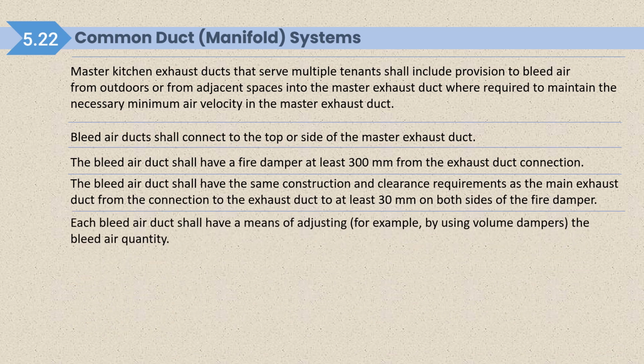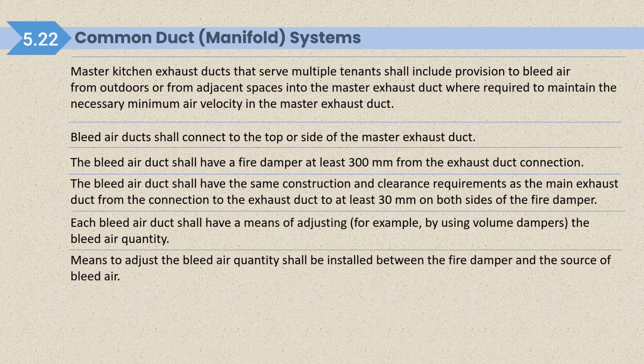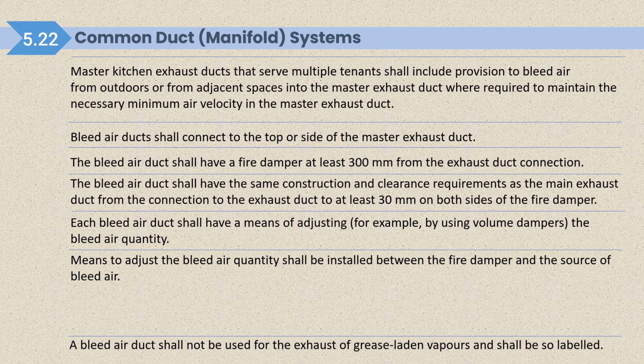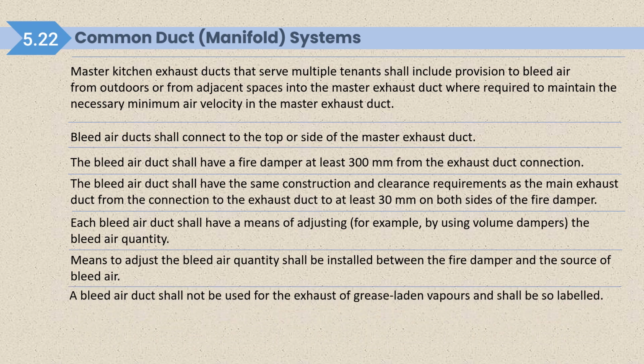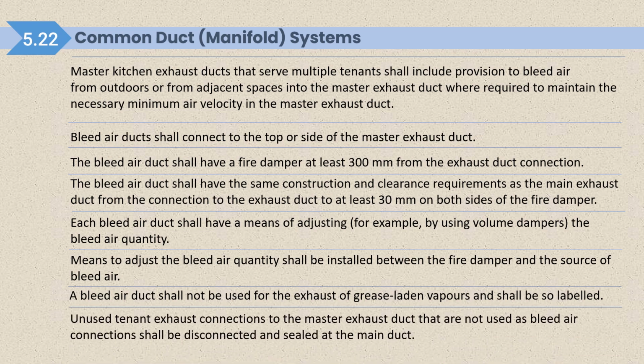Each bleed air duct shall have a means of adjusting, so air flow can be adjusted by using volume damper. Means to adjust the bleed air quantity shall be installed between the fire damper and the source of the bleed air. A bleed air duct shall not be used for exhaust of grease laden vapor and shall be so labeled. Unused tenant exhaust connection to the master exhaust duct that are not used as a bleed air connection shall be disconnected and sealed at the main duct. Whenever any tenant left, we have to make sure that exhaust connection is completely sealed and closed, disconnected.